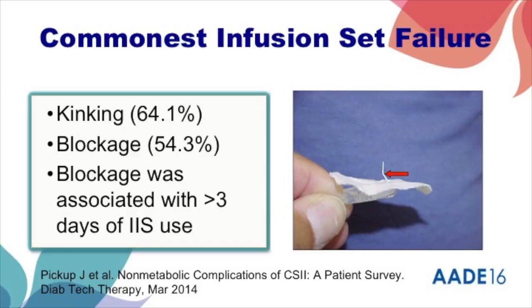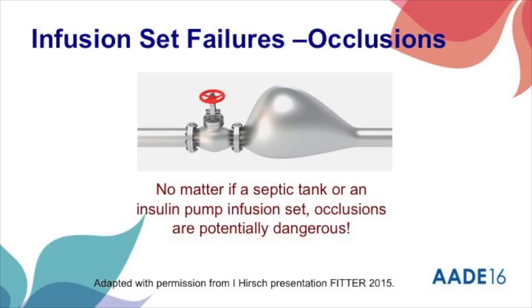The commonest infusion set failure is kinking or blockage, and it occurs more often if the sites are left in longer than 3 days. Occlusions, whether silent or alarmed—if you have a failure, no matter if it's a septic tank or an infusion pump set, occlusions are potentially dangerous.